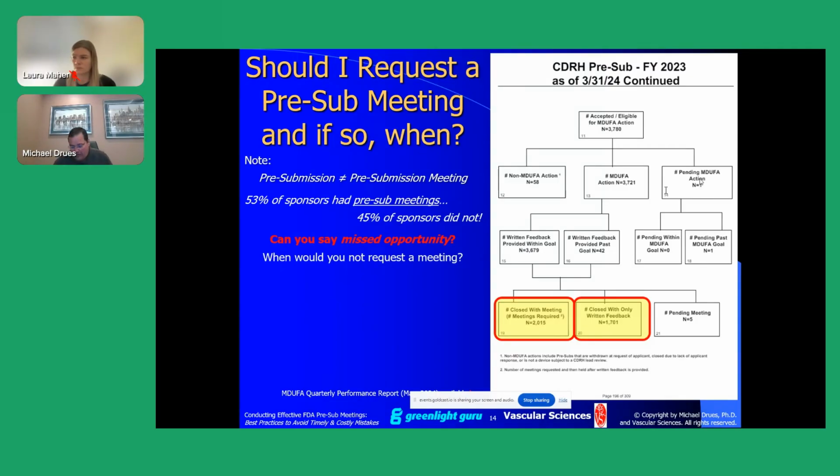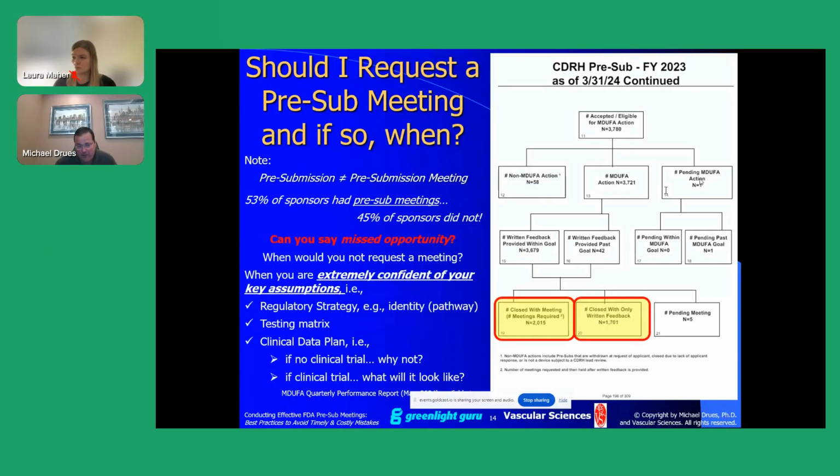So when would you not request a meeting? As I said a moment ago, virtually always I will request a meeting. If you're extremely confident in the key assumptions to bring your product onto the market, and three of the biggest for me are your regulatory strategy, for example, 510K, de novo, PMA, HDE, whatever, your testing matrix. This is a list of all of the tests that you have either done already or are planning to do to show that your product is safe and effective, to make sure that you can meet the label claims and so on, and your clinical data.